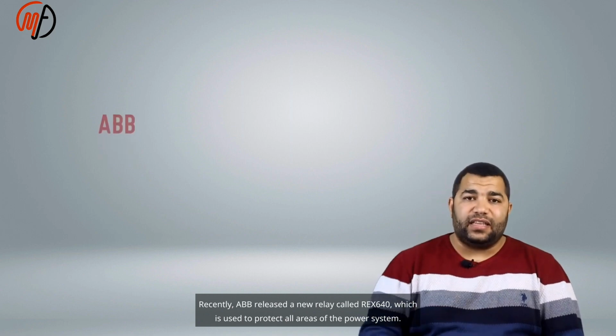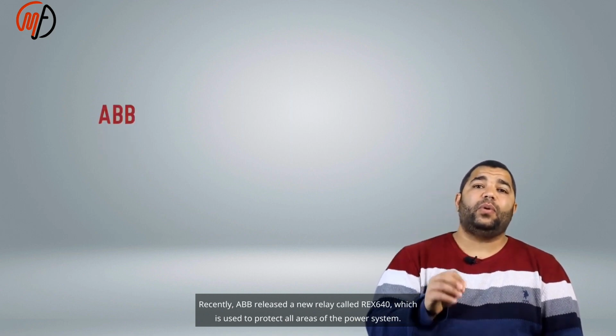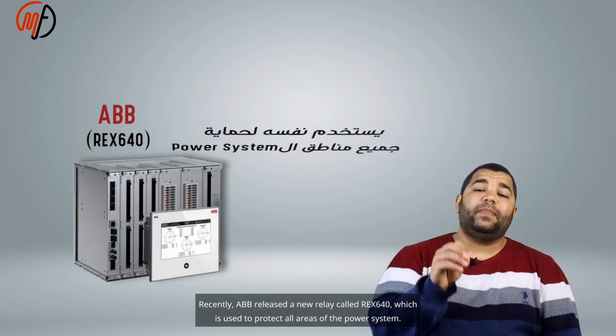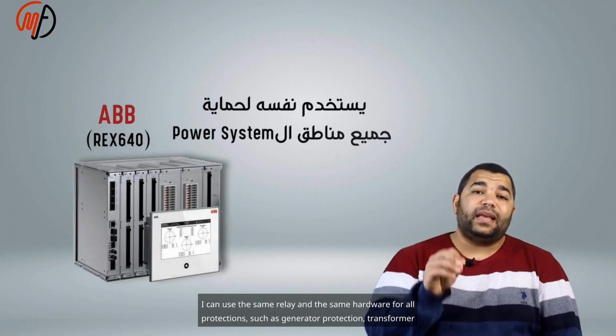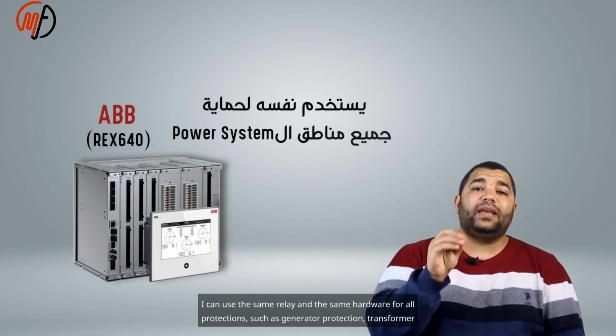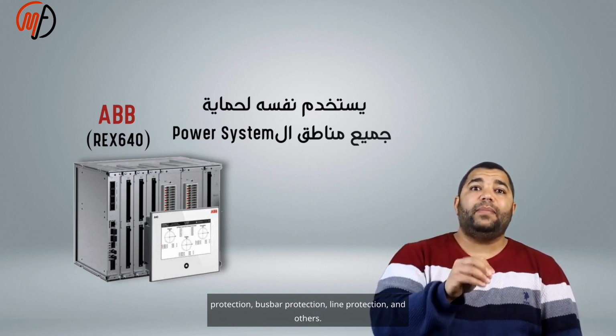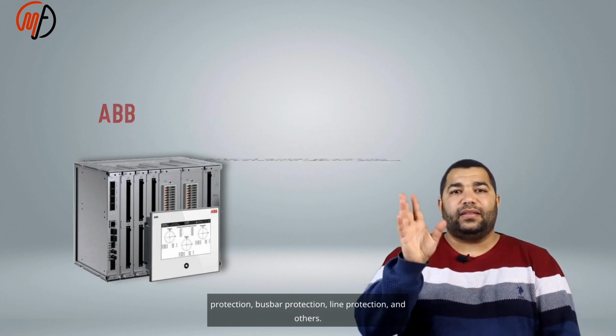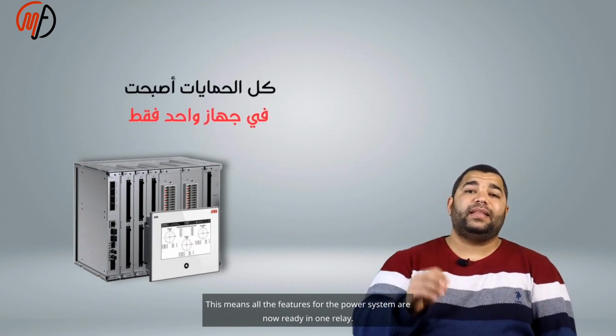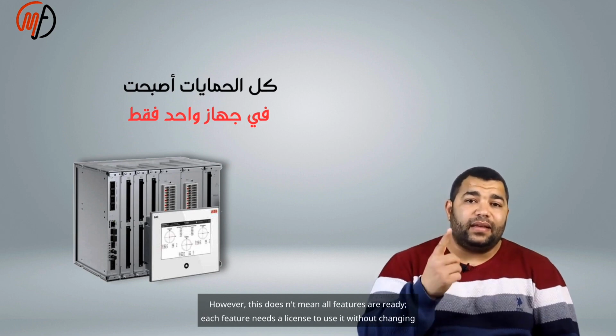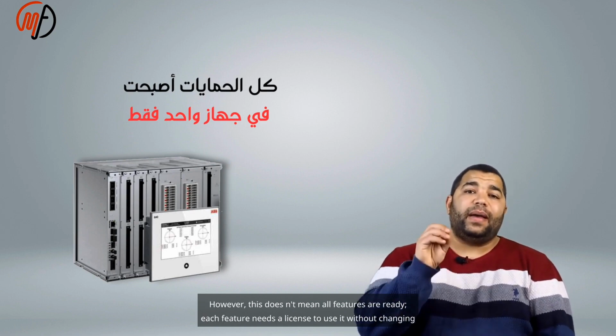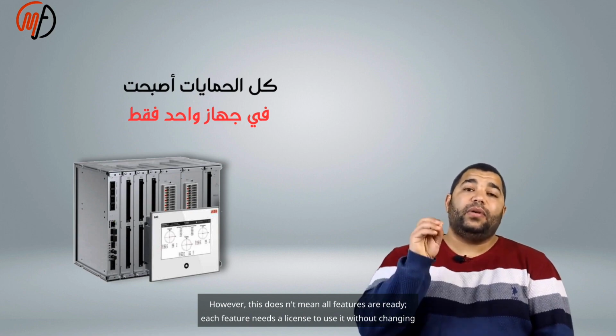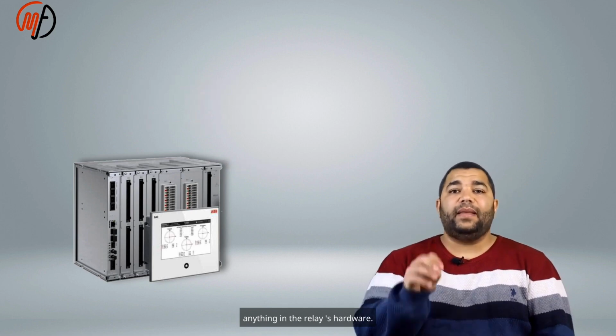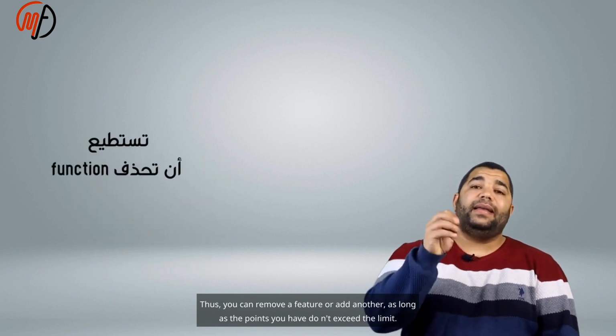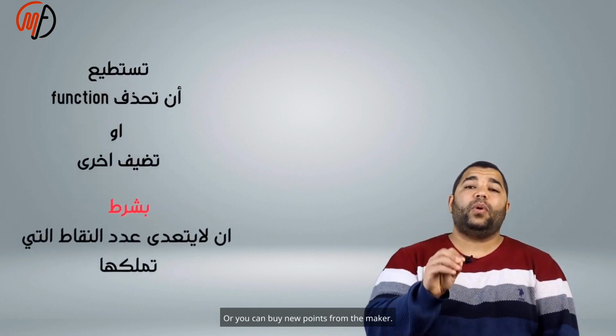Recently, ABB released a new relay called REX 640, which is used to protect all areas of the power system. I can use the same relay and the same hardware for all protections, such as generator protection, transformer protection, busbar protection, line protection, and others. This means all the features for the power system are now ready in one relay. However, this doesn't mean all features are ready. Each feature needs a license to use it without changing anything in the relay's hardware. Thus, you can remove a feature or add another as long as the points you have don't exceed the limit, or you can buy new points from the maker.